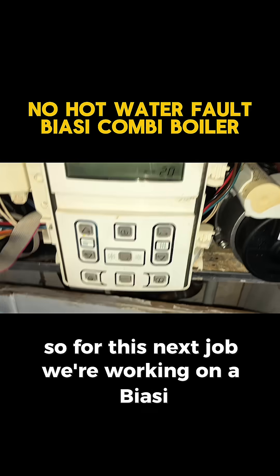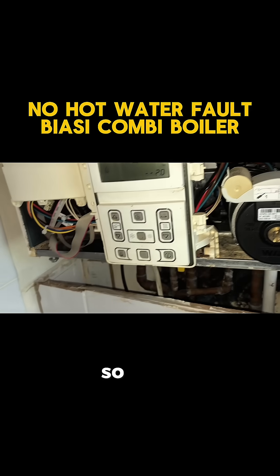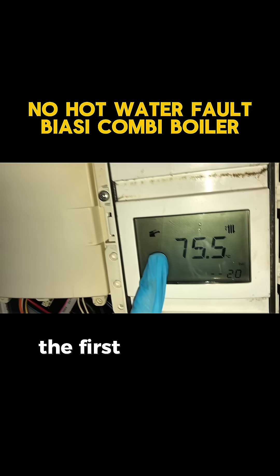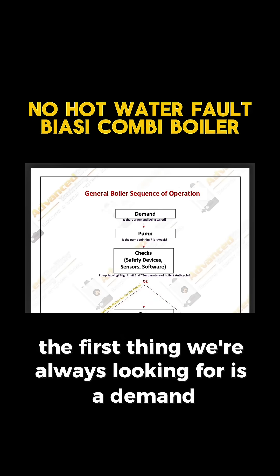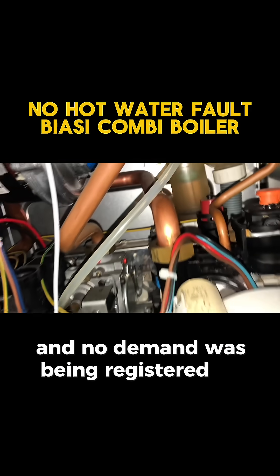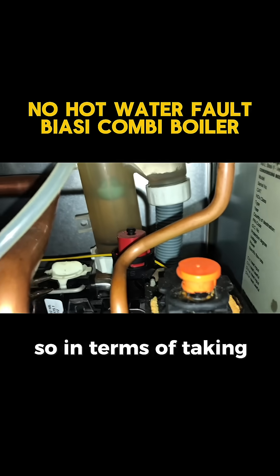For this next job we're working on a Biasi and the issue is the hot water is not working at all. Referring to the cheat sheet I made, the first thing we're always looking for is a demand. I tried running all the hot taps in the house and no demand is being registered on the boiler, so usually that is just a flow turbine.